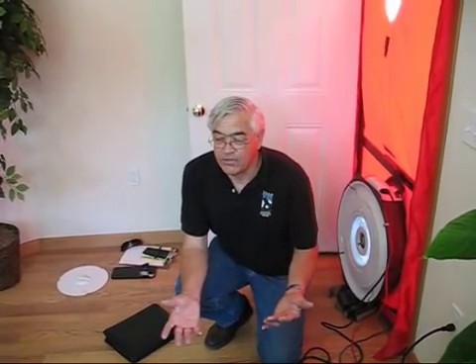When we do the blower door test, we close all the windows in the house, shut the vents, turn off the whole house fan. We don't do anything to the vents as far as keeping them taped over or anything like that to the outside — it allows them to naturally do it.